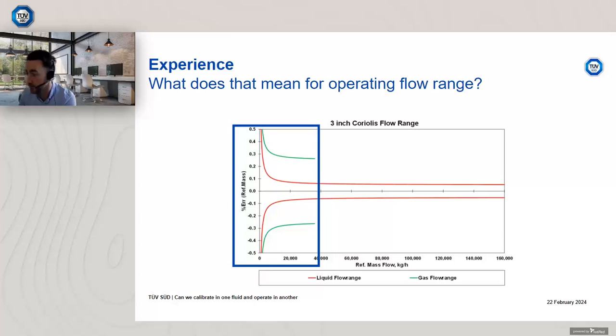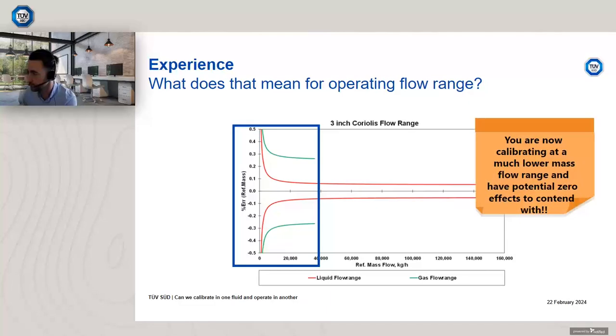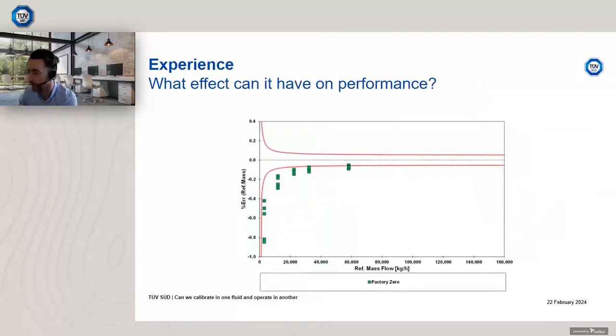And as such, if you try and calibrate a gas meter in liquid at the same gas flow ranges, you're operating a very small part of the flow range, which is a real challenge. So you'll have potential zero effects to contend with, something you should be aware of. So before I go back to show you some gas data, I want to discuss zero effects. So what are they? And what effect can they have on the performance?